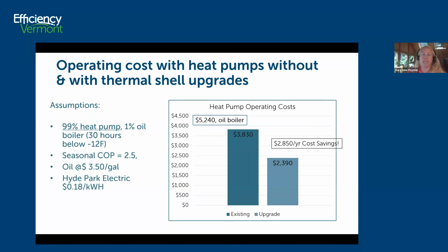So let's look at the operating costs of the heat pumps with and without the thermal shell upgrades. The main assumption is that you're going to pick up 99% of the oil with heat pumps, and you'll still be using the oil boiler 1% of the time, a seasonal COP of 2.5, oil at $3.50 a gallon, and Hyde Park at 18 cents a kilowatt hour. So the original cost for the oil boiler per year was $5,240 to operate. Then switching over to heat pumps, but without any thermal shell upgrades, was $3,830. And now doing thermal shell upgrades and heat pumps, your operating cost is $2,390. So you've cut your operating cost in half by making these upgrades, which is great.